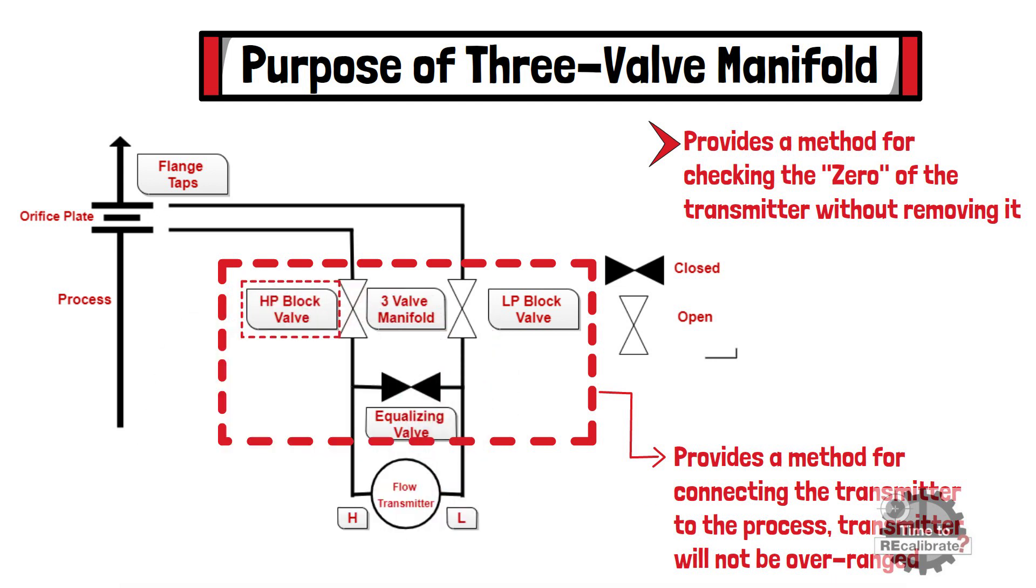The three valve manifold consists of two block valves and one equalizing valve. The block valves isolate both the high and low pressure impulse lines, while the equalizing valve ensures the pressure difference between the high and low side remains effectively zero during the process of removing from service or putting into service.